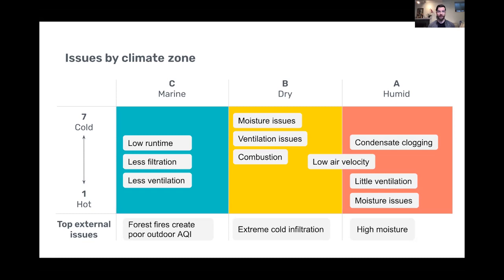And so we see a lot of particulate events, particularly in the summer, where it's quite an issue because you have to shut your ventilation off now. You can't bring in that outdoor air unless you filter that outdoor air first. But we see a lot of people just shut off their ventilation for potentially multiple months during the year. And therefore, not only are they getting low runtime on their HVAC equipment, and so not getting a lot of filtration or runtime and air mixing, but they're also not getting any ventilation. So they go from the extremes of the best air quality in the world to the worst air quality in the world, depending on the season.